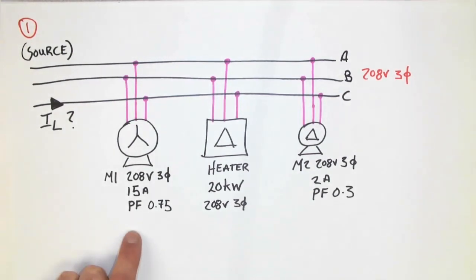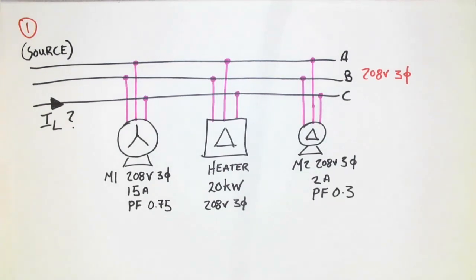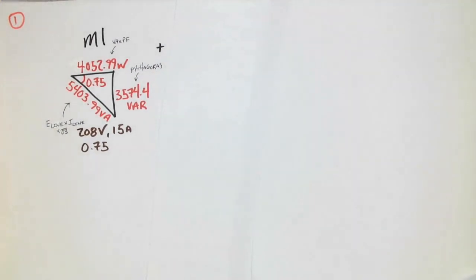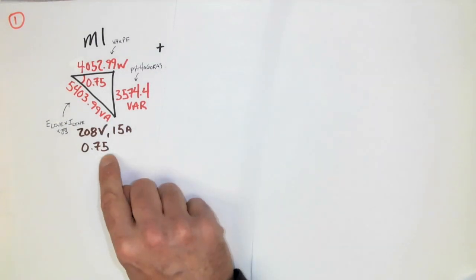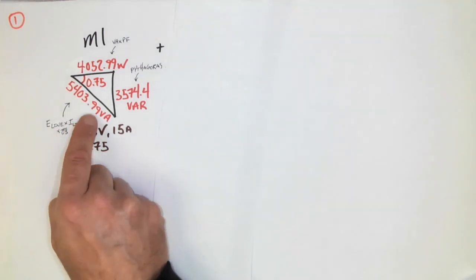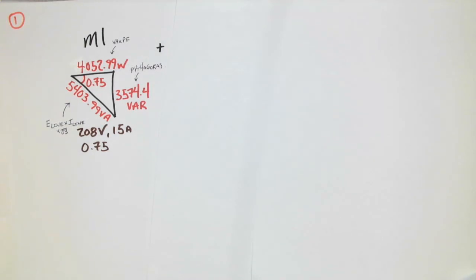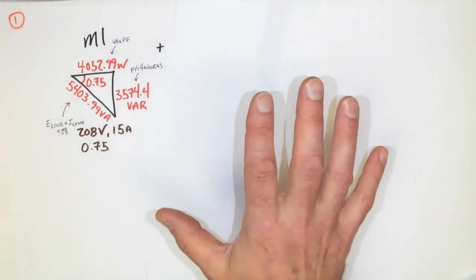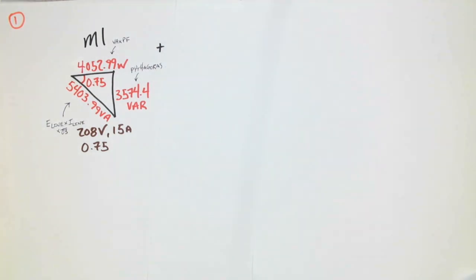So the first step is to sketch a power triangle for each one and calculate all of the different sides of those power triangles. For motor one, I make my first power triangle labeled M1 — 208-volt, 15 amp, 0.75 power factor. Using E-line times I-line times root three, I get the total VA. I multiply by 0.75 to get my power, and then use Pythagoras to get my VAR value of 3574.4. This is not the only way to accomplish this — it's one of many.